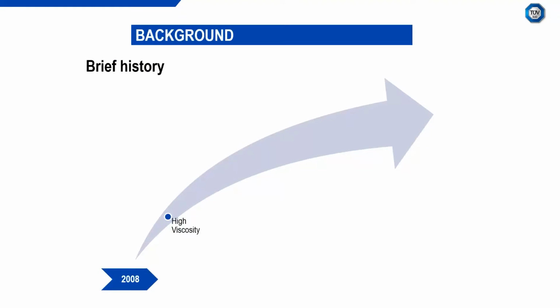orifice meters as well. So we kind of looked at a vast array of conventional liquid flow meters to see how they performed with medium to high viscosity fluids. So this ranged from typically 50 to 2000 centipoise, so fairly viscous. We operated right across the laminar, transitional and turbulent flow regimes. We then followed that up, in 2010, by looking at the effects of elevated temperatures on flow meters.